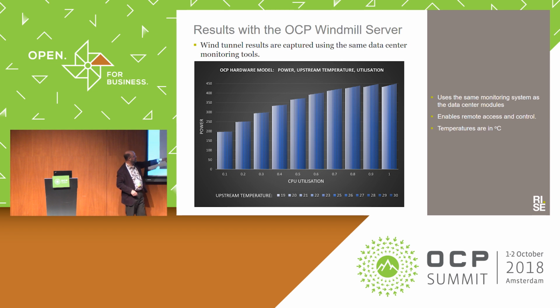This doesn't show delta T, just power consumption at the moment. But it shows that as you increase to 80-90% utilization, there's a difference in power consumed between 19 degrees and 30 degree inlet temperatures. That's a combination of power drawn by the fans, since we're not controlling the fans yet in this example, plus possibly some current leakage. There's a bit of both.